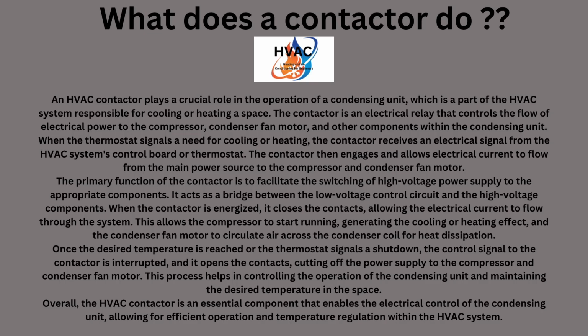Now when it specifies control voltage, anything that is control voltage is going to be low voltage. 24 volts in this system for a residential home system is 24 volts. Basically, it feeds your thermostat, your board cycle that's inside your furnace, and then the contactor that it feeds to outside.